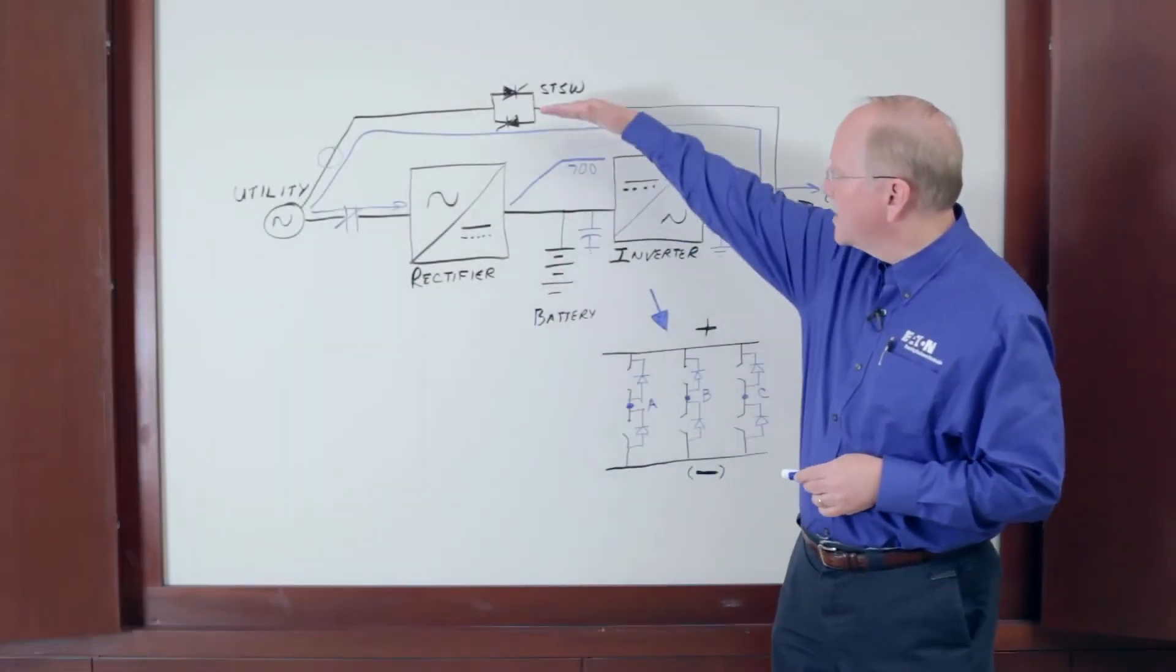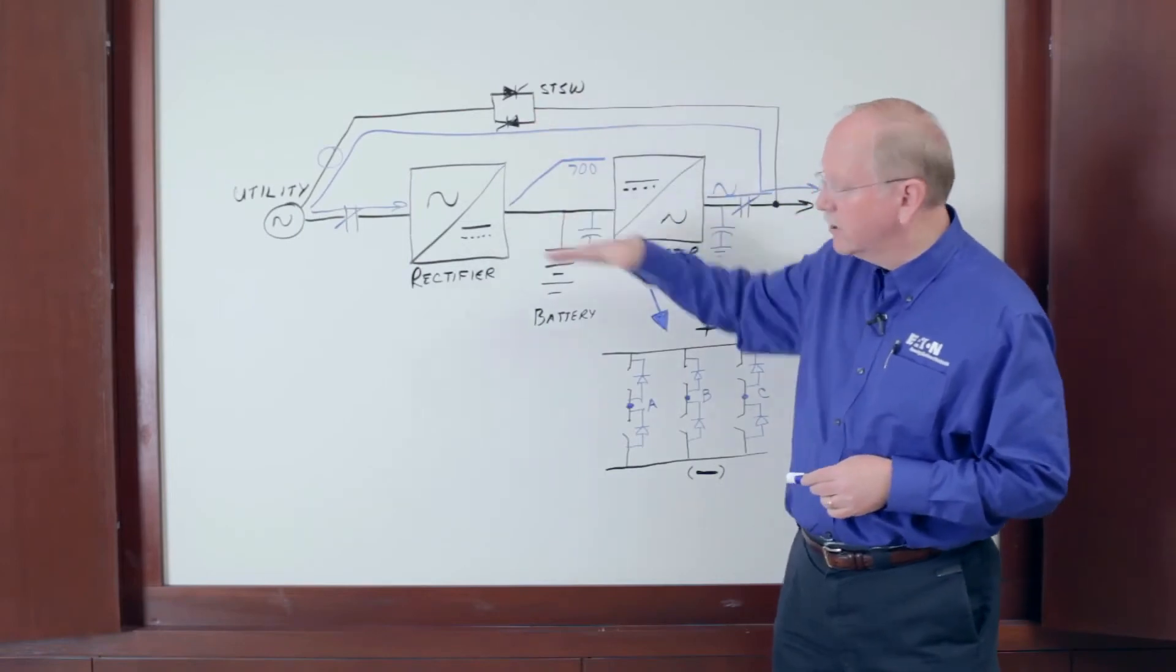So if you're considering using eco mode on your UPS, there's three criteria that should be important. The first one is transition time. The time it takes from static switch operation to traditional double conversion should be less than four milliseconds, ideally less than two milliseconds or two 1,000th of a second.